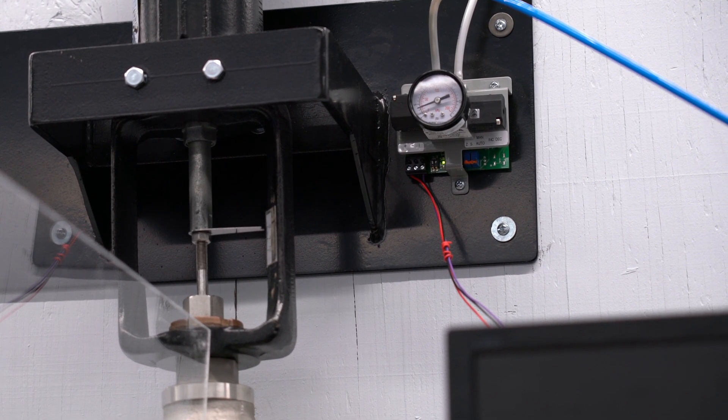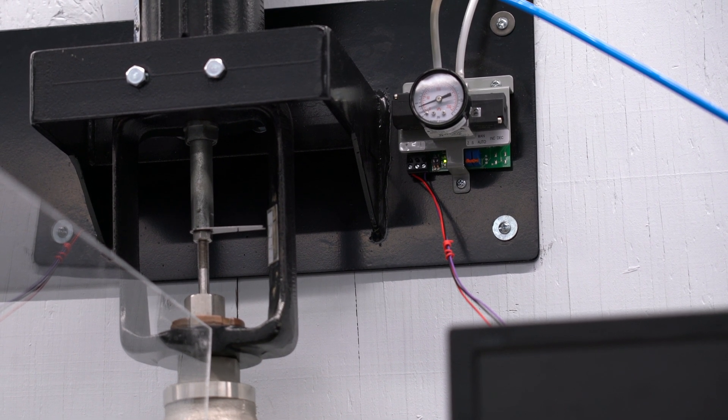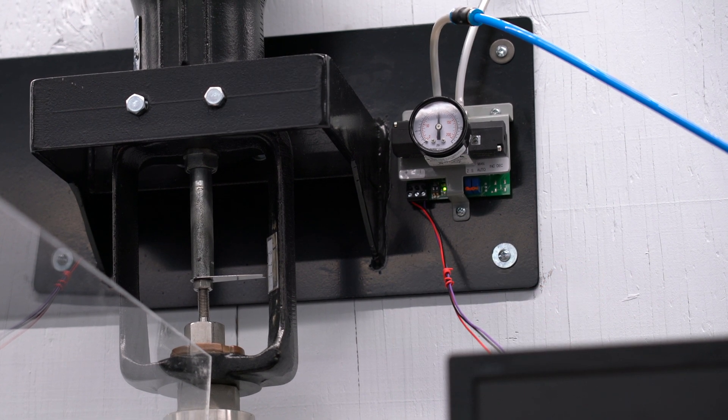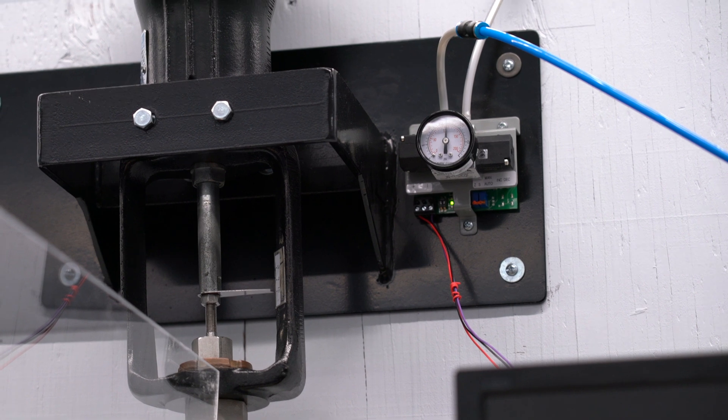So I'm at 0 volts and the pressure is 3 psi. If I go up to 10 volts again, that pressure is going to go up to 15 psi again.